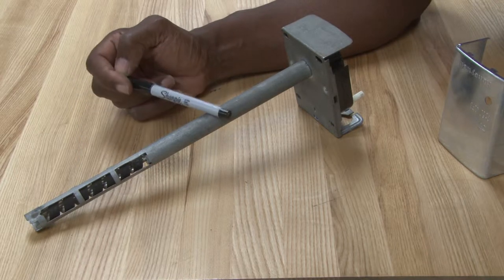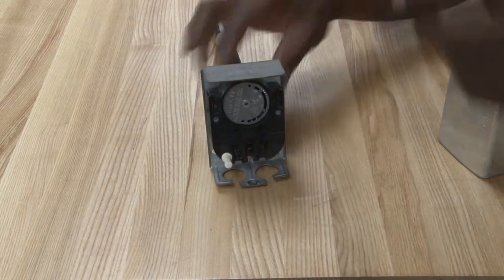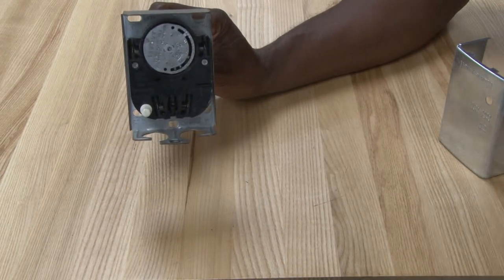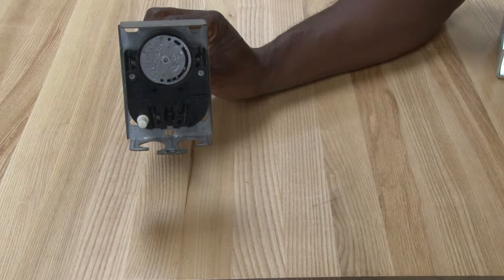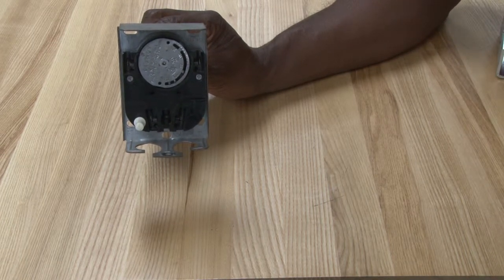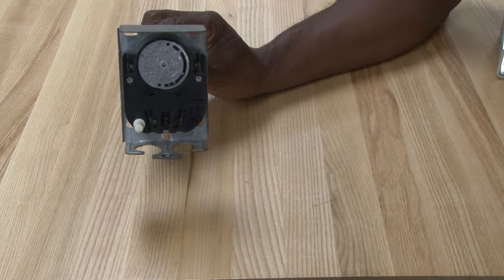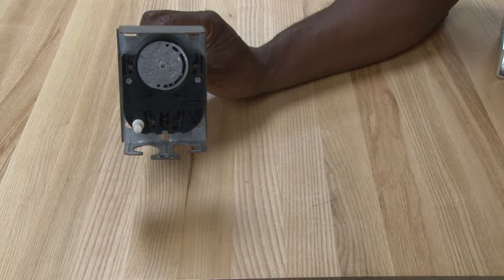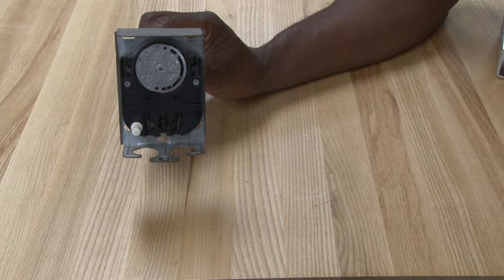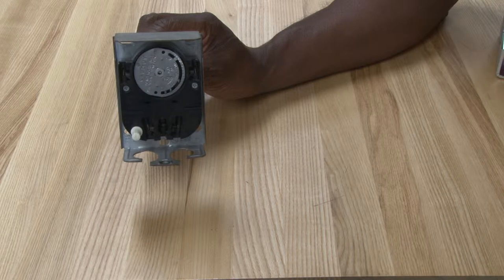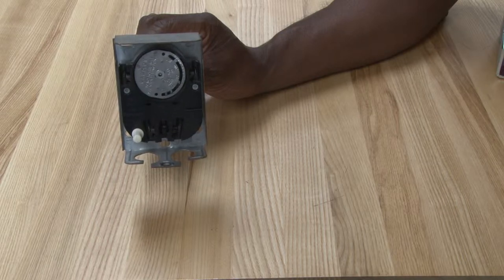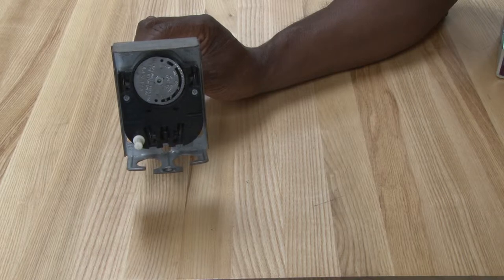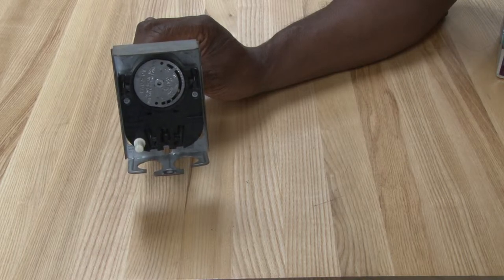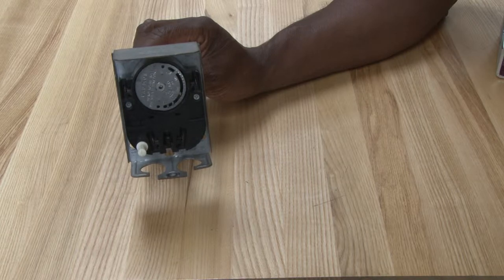But also, this same control will control the operation of the blower motor. The blower motor will delay turning on based on the temperature that's built up inside your heat exchanger. So when the temperature gets to the correct amount, where there's heat that can be used to circulate through the house, at that point this control will bring in the operation of the blower. And so it would be set by the technician for the proper temperature as it operates the blower motor.